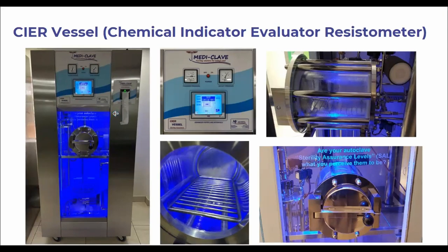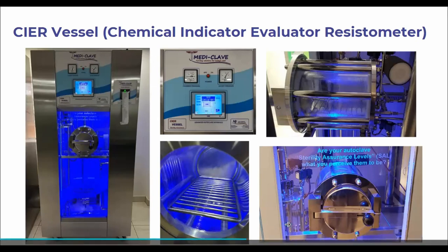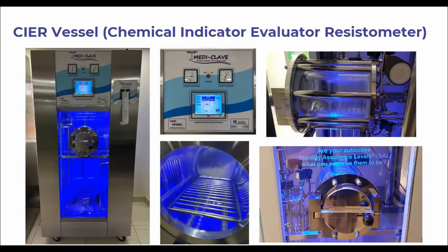All right, thank you, Janita. Yes, I'm just going to talk briefly about the CIER vessel. The CIER vessel was designed to expose microorganisms or biological and chemical indicators to defined steam sterilization reference conditions in a range from 110 to 134 degrees. It produces a square wave profile for pressure, vacuum, and temperature under real steam sterilization conditions. Due to the high accuracy, it's particularly suitable for the determination of the activation kinetics, the resistance of the microorganisms, chemical reaction kinetics, and material behavior. An essential tool for product development, quality control, and process optimization in steam sterilization technology.